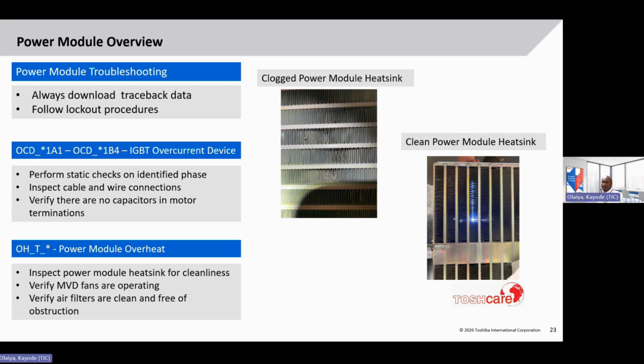First thing to do, if you see overheat fault, after downloading the traceback data and of course locking down the drive, is to inspect the power module heatsink for cleanliness. A clogged power module heatsink, like shown in the picture on the left, will cause an overheat. It might not be right away, but eventually, because airflow needs to be unobstructed through the heatsink to make sure that the power devices are properly cooled. And this fault will be detected by the temperature switch I mentioned.